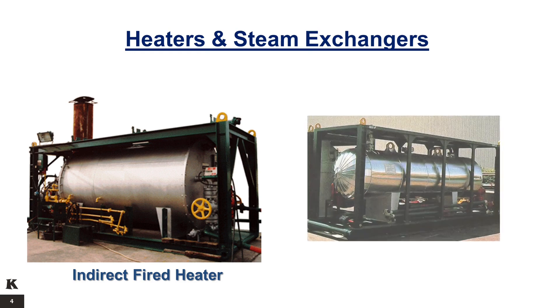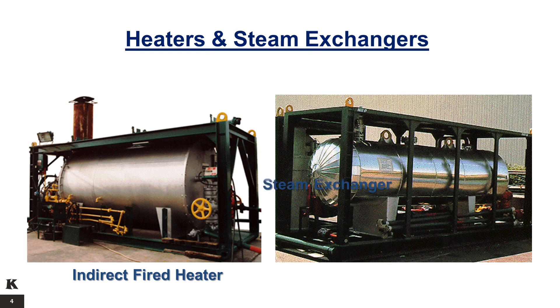Steam exchanger. Because steam heat exchangers drastically reduce risk, they are used on offshore platforms and in other work conditions where safety regulations do not permit the use of indirect fired heaters. The steam heat exchanger is a steam vessel with two coils through which the well fluid passes. A choke assembly between the coils enables the well to be controlled at the steam exchanger instead of at the choke manifold.